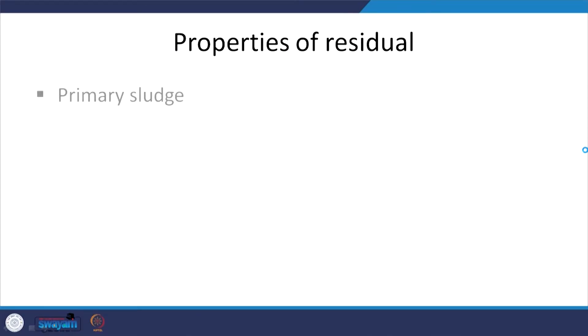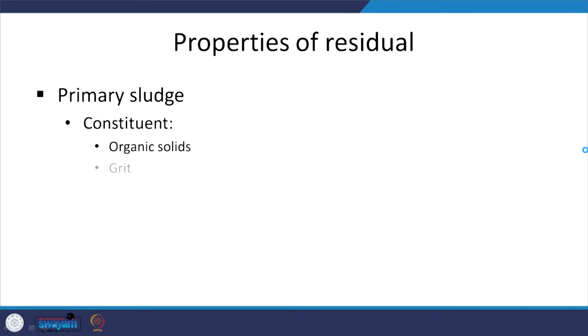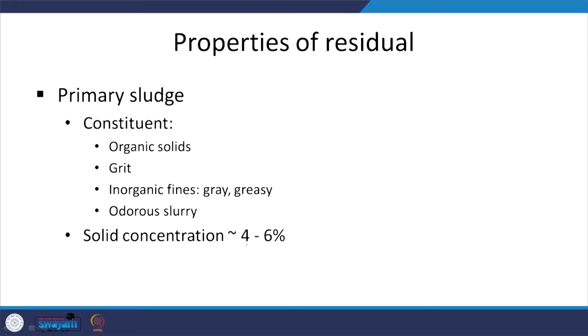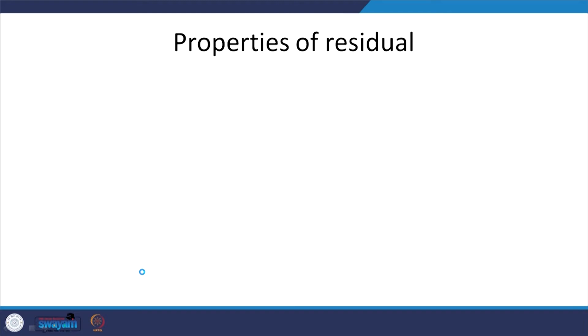Maybe that is going to change soon. Properties of the residual or sludge: for primary sludge — mostly considerable organic solids, grit, inorganic fines, and it is quite odorous; it is a slurry. Solid concentration is not very high but is still high enough — 4 to 6 percent — and organic content is high: volatile suspended solids 60 to 80 percent.